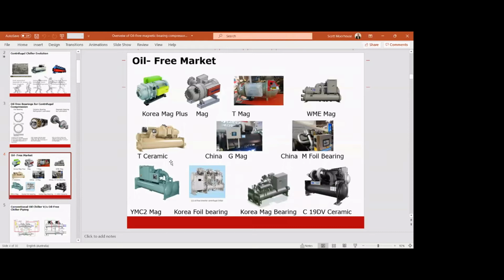Gree have magnetic. Midea have a foil bearing, which they are quite rare in those capacities for what Midea are doing. York is using a magnetic single stage compressor. In Korea, we have a company developing foil bearings and limited to about 100 ton or 300 kilowatts. And they're also doing magnetic bearings as well. And then Carrier bring out the 19DV, which is an R1233 negative pressure ceramic bearing chiller.